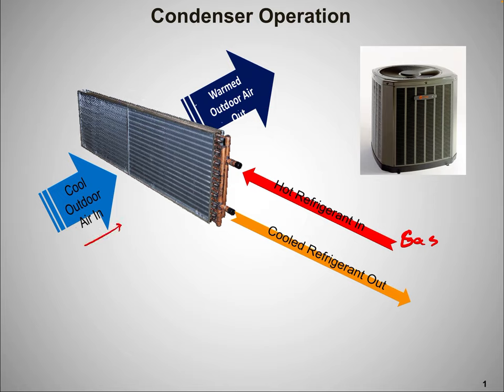We expect cooler outdoor air to come in, and we expect it to become warm as it pulls some of the sensible heat from the refrigerant. That's the basic expectation of the system. One way I can tell if a unit is not pulling out a lot of heat is by the difference between the cooler outside air coming in and the warmer outside air going out. When those two temperatures are very close together, we're not really pulling much heat out — something is not right.